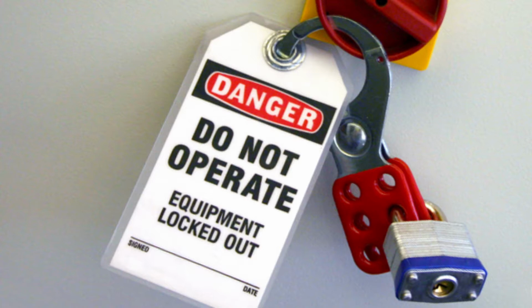If more than one person is inside the confined space, each person will place his own lock on the circuit breaker. In addition to the lockout system, there must be an accompanying tag that identifies the operation and prohibits use. Disconnecting couplings or removing drive belts or chains can achieve mechanical isolation of moving parts. Equipment with moving mechanical parts will also be blocked in such a manner that there can be no accidental rotation.